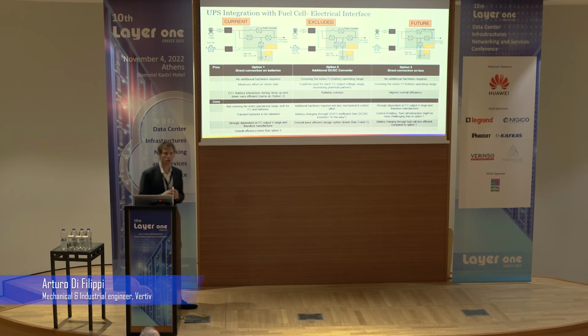Option one is what we could do now, and I'll explain why. This means connecting the fuel cell to the lithium-ion batteries, keeping the configuration in DC. This can improve efficiency because you have one less conversion - you don't go to AC, like with the diesel generator where you have the inverter. Here you keep everything in DC, and you can also benefit from the batteries absorbing the power transients typical of the fuel cell, since fuel cells aren't able to react to power transients as quickly as diesel generators - they need to dissipate some power, which is why using batteries helps.